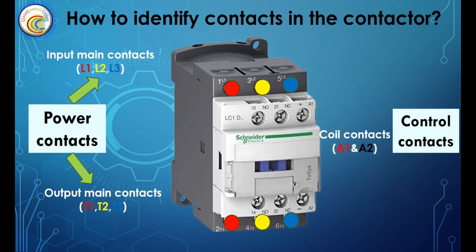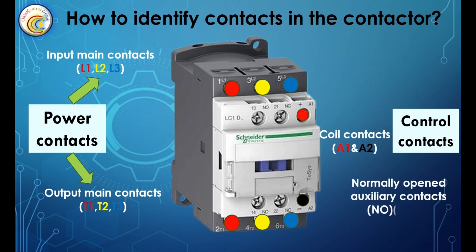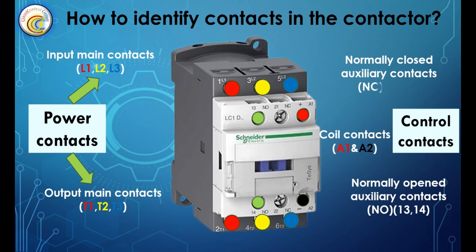Normally open auxiliary contacts are labeled N.O., or terminals 13 and 14. Normally closed auxiliary contacts are labeled N.C., or terminals 21 and 22.